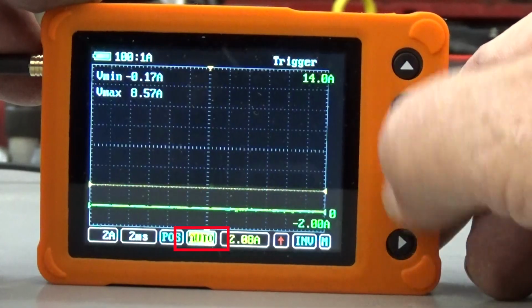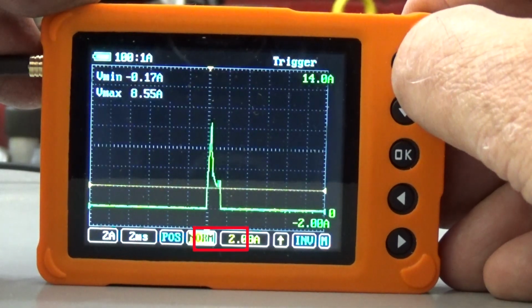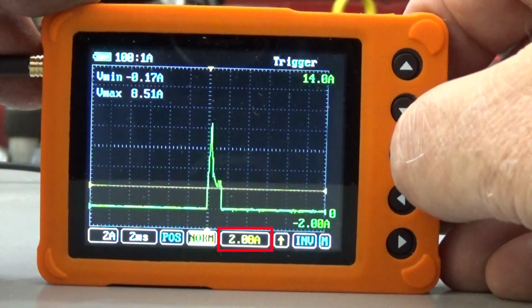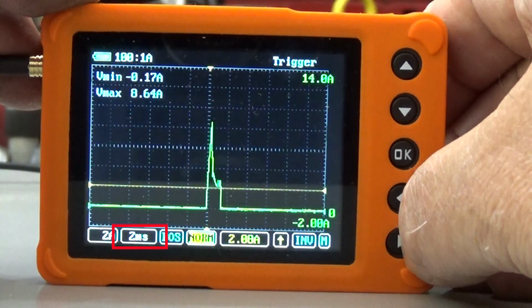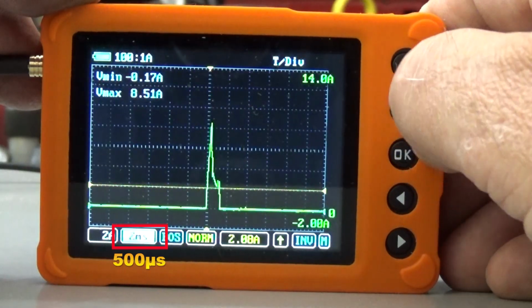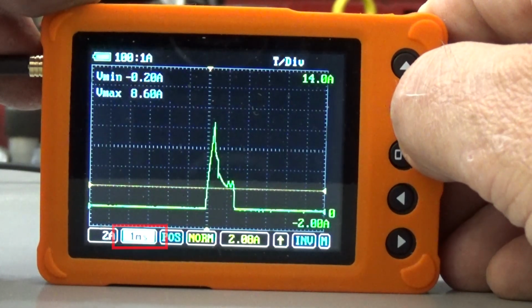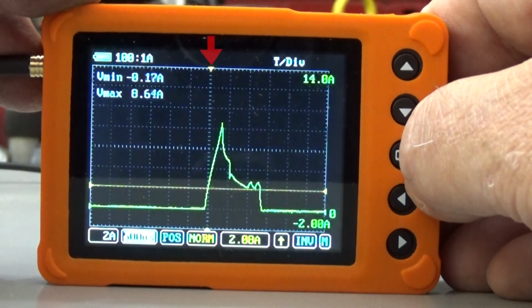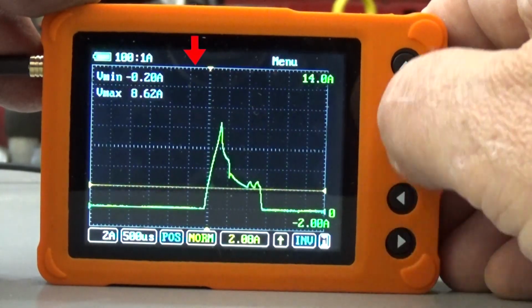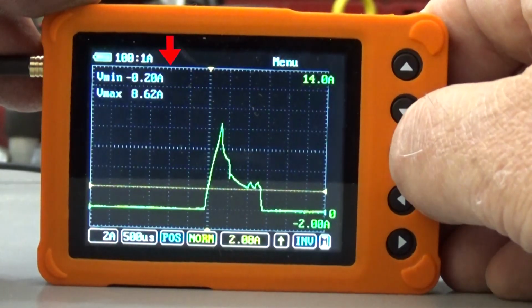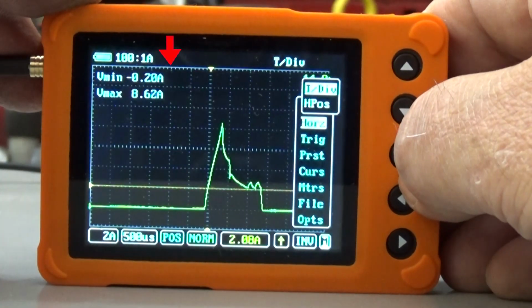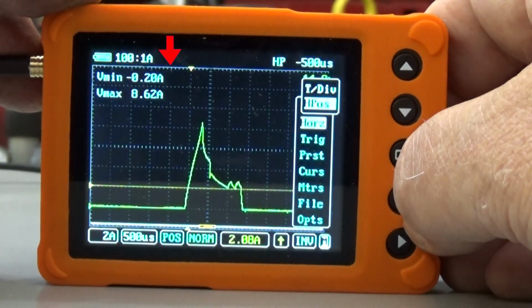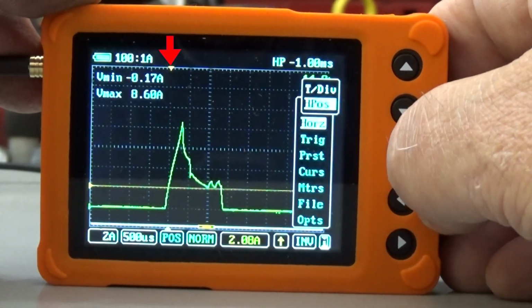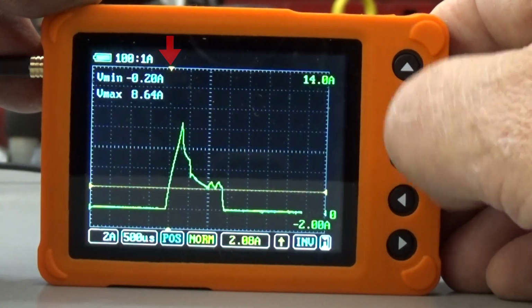Set the trigger to normal on the rise with a threshold of 2.08 amps. Then reset the horizontal sweep scale to 500 microseconds per division. As a personal preference, I will shift the horizontal trigger 2 graduations to the left. To do this, navigate to the menu, select horizontal, select HPOS, and press the left arrow twice, then OK.